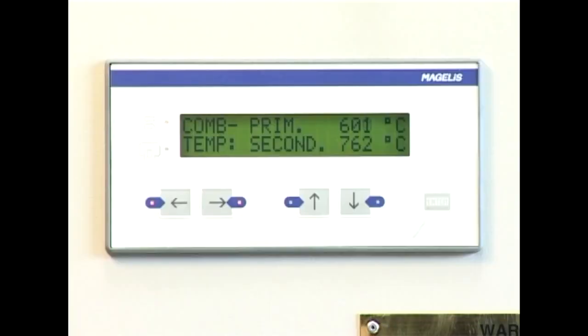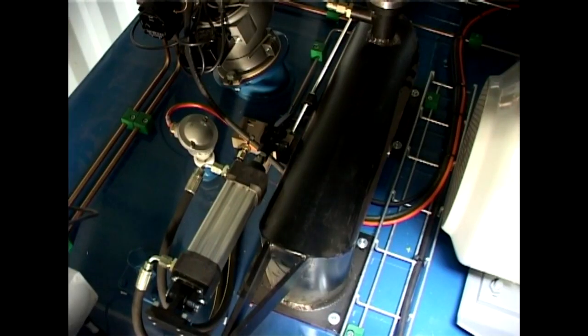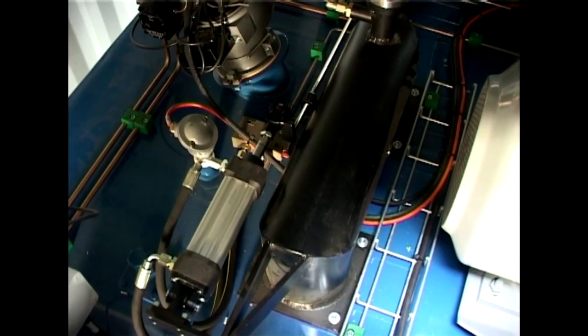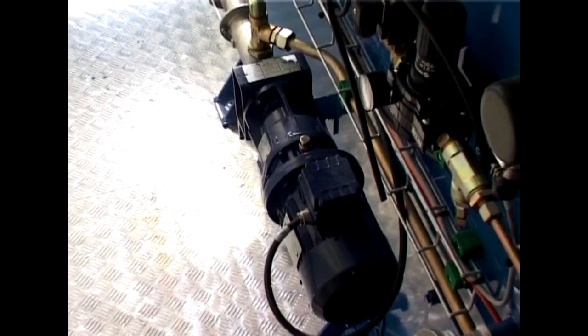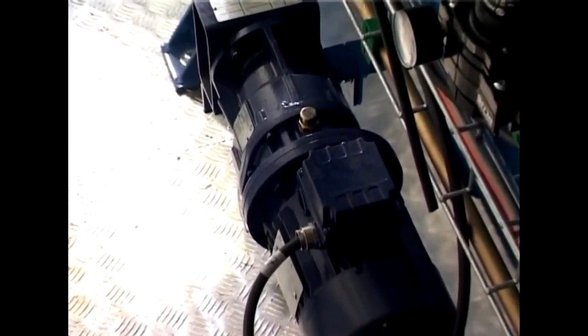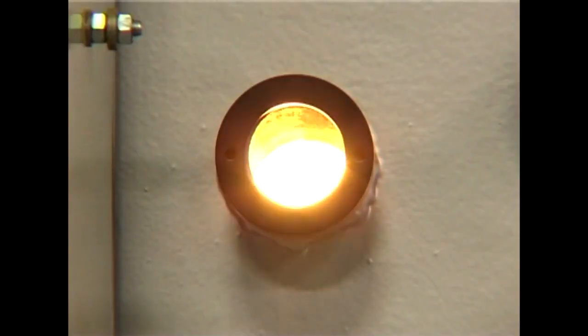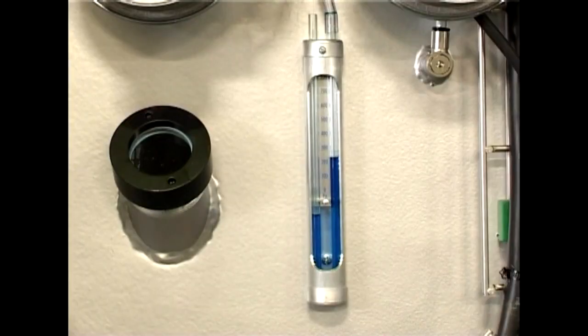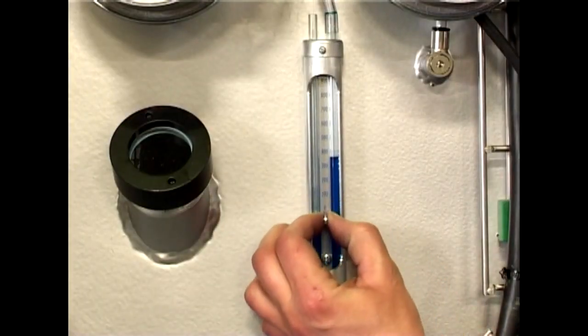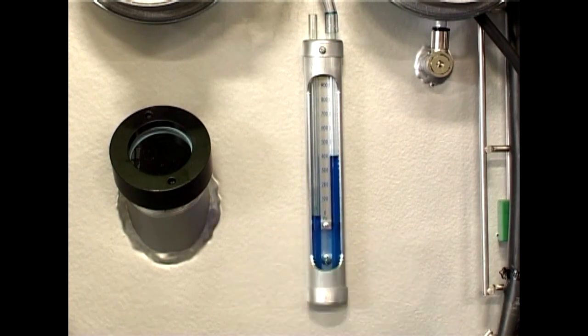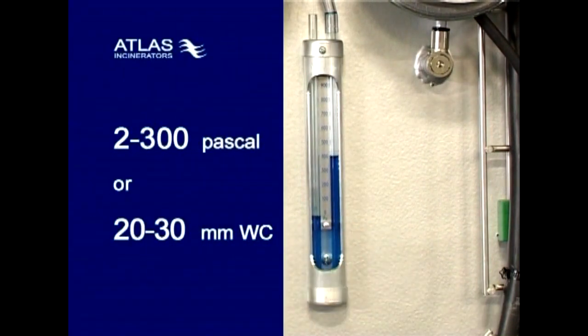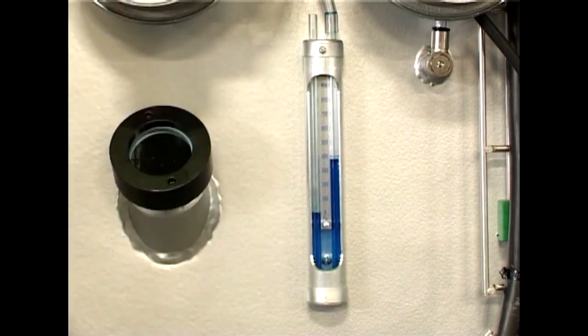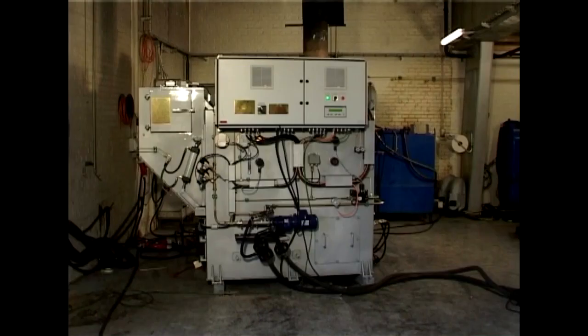When the temperature in the primary combustion chamber reaches 600 degrees Celsius, the sludge burner damper will automatically open and the sludge dosing pump will start dosing sludge into the combustion chamber, which will be ignited by the primary burner. Monitor the vacuum in the combustion chamber and adjust the damper on the mixing chamber to be 200 to 300 Pascal. Now, the incinerator is ready for incineration.